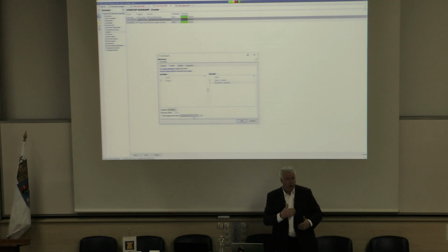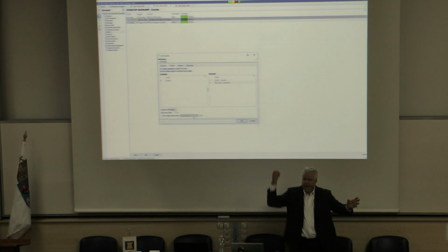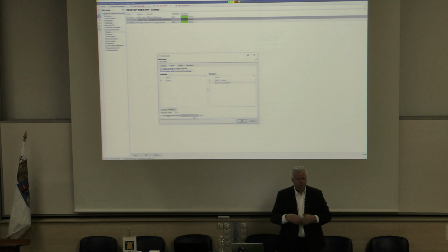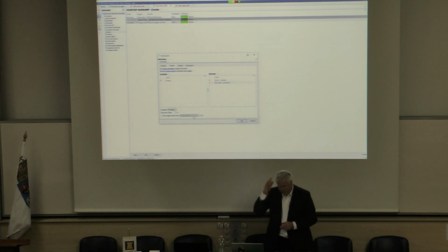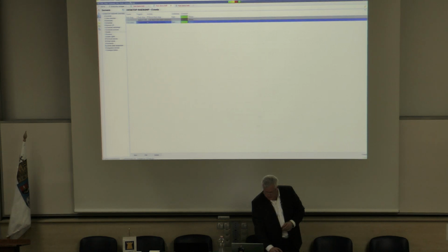This would be populated and configured according to the type of device that you're connected to. So it's an access control system. If I saw a door forced and the PIR in the room picked up motion, these two conditions say that I must send an alarm to this person. This is when you can start to generate intelligent triggers, intelligent alarms and avoid a lot of the false positives that we see in the industry today. So the event configuration here is very powerful.